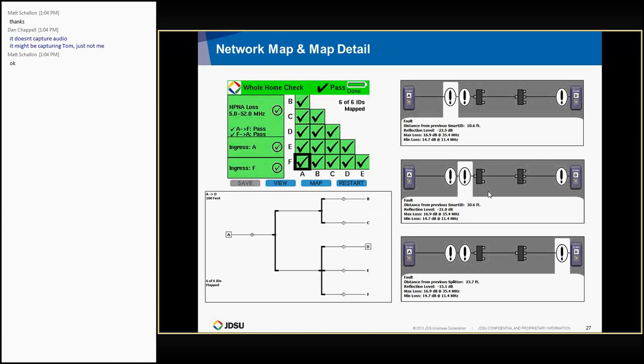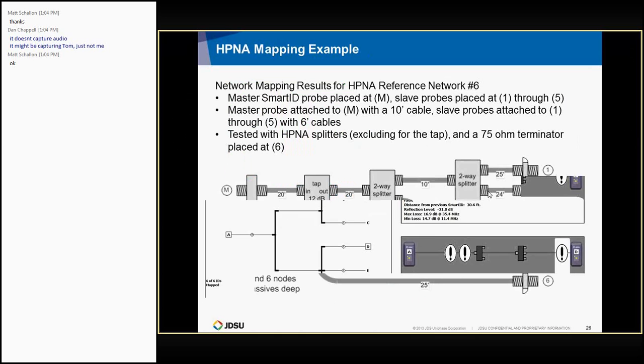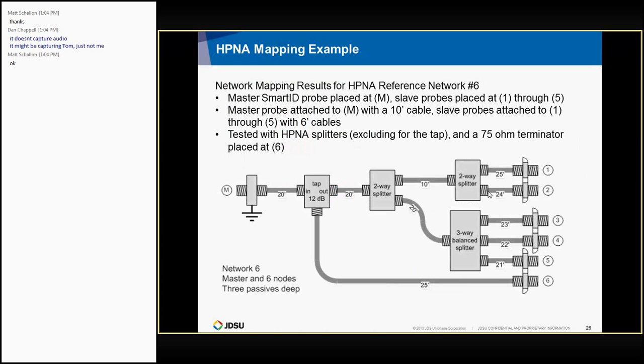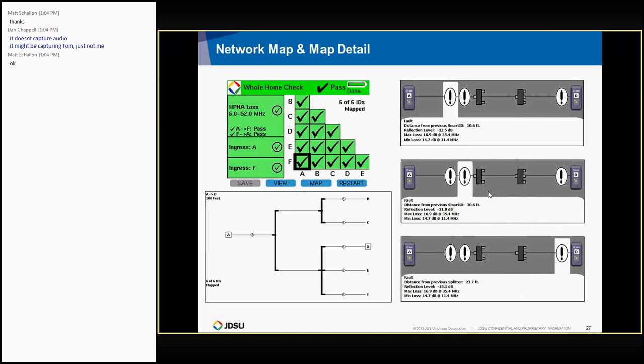The first reflection is reported at 10.6 feet, which is the length of the cable that attaches from the Smartid to point M on the reference network, from the master probe to point M. Then you have 20 feet to the tap. And if you look at the next one beneath it, it reports the second reflection at 30 feet, which is 20 feet beyond the one above it. That's where the tap is coming into play.